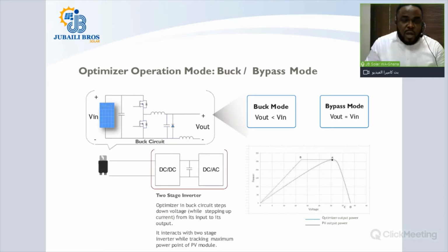Okay, so I was explaining the two types of mode that the optimizer operates in. So we have the buck and the bypass mode. In the bypass mode, as you can see from this graph, the lower line here is the output of the PV module, and the upper line, the blue line, is the output of the PV optimizer. In the bypass mode, the PV optimizer does not change the current or the voltage output of the PV module. It only optimizes these values. It does not change them.